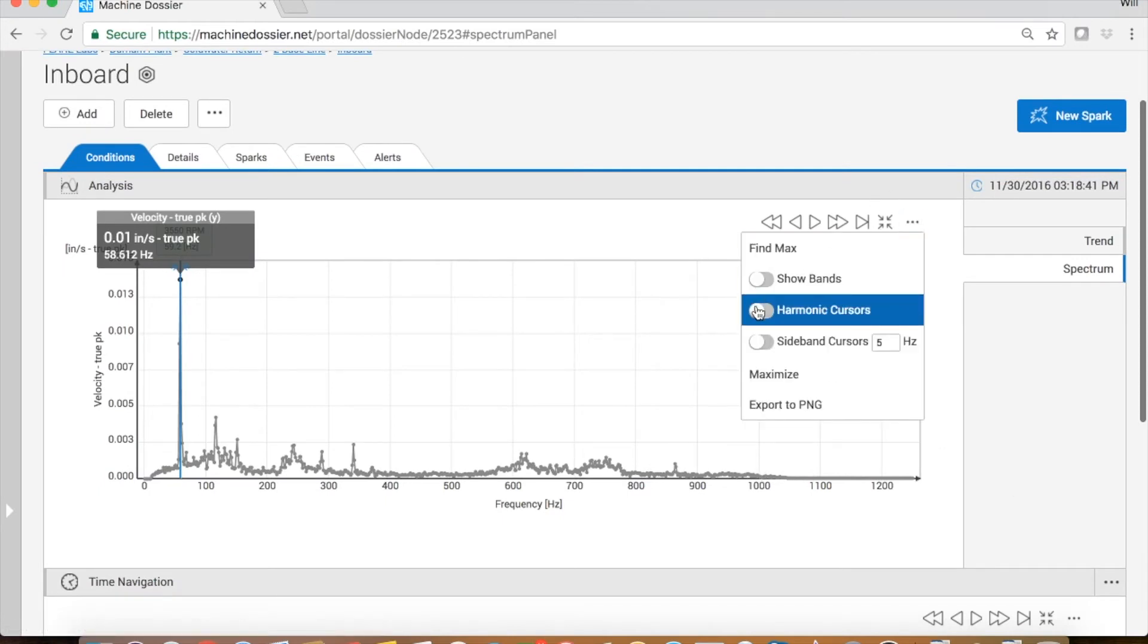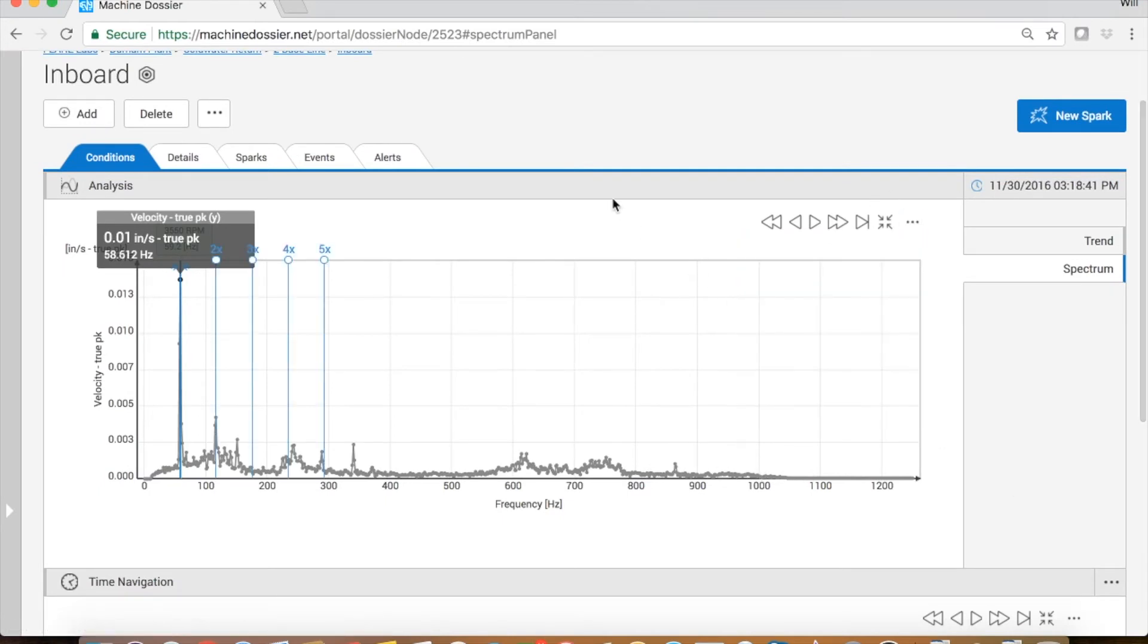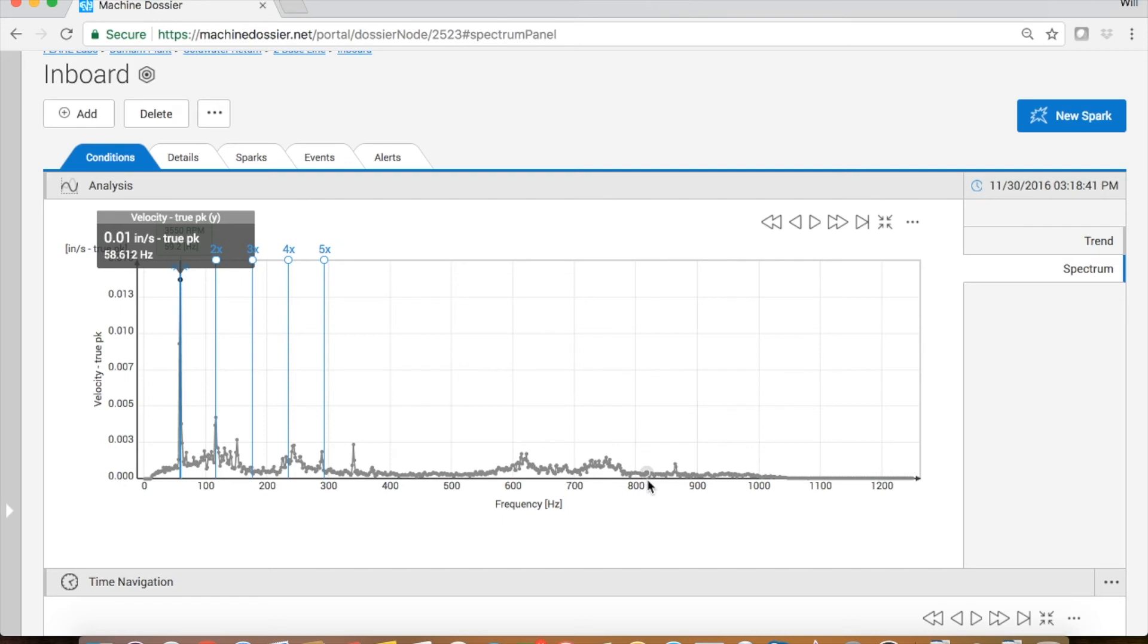First thing we'll do is add the harmonic cursors and that allows us to easily see which components comprise this spectral data. Most of the vibration is occurring at one times RPM vibration with a little bit at two times and then a few other frequencies and some broadband noise scattered across the spectrum. This is exactly what we would expect for the baseline on a brand new pump. A little bit of unbalance and a little bit of misalignment, but all the values are very, very low.